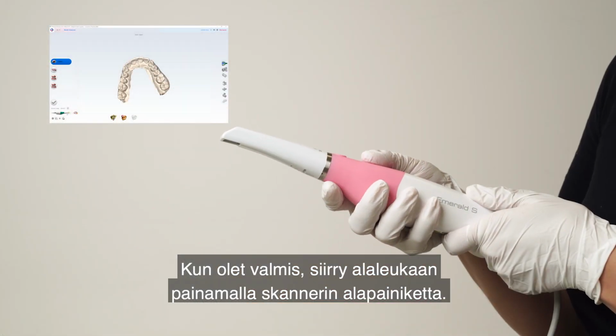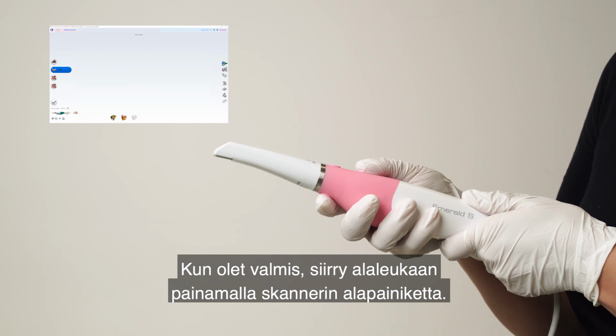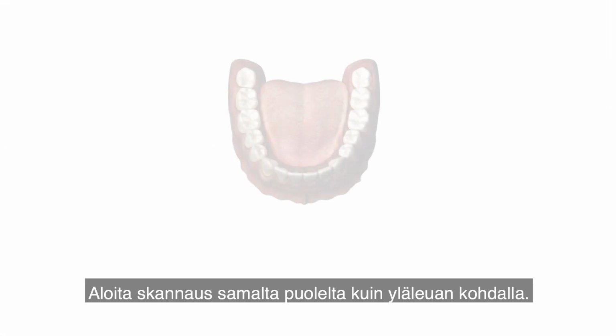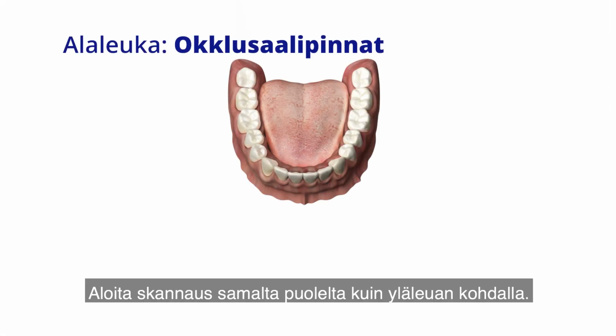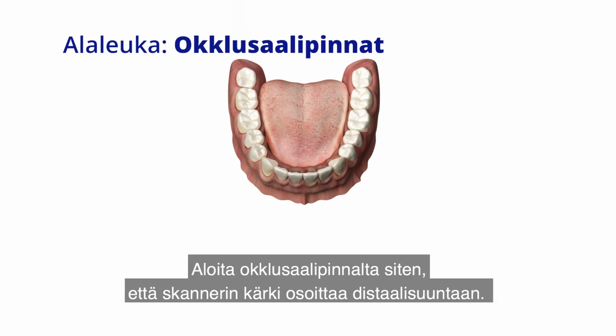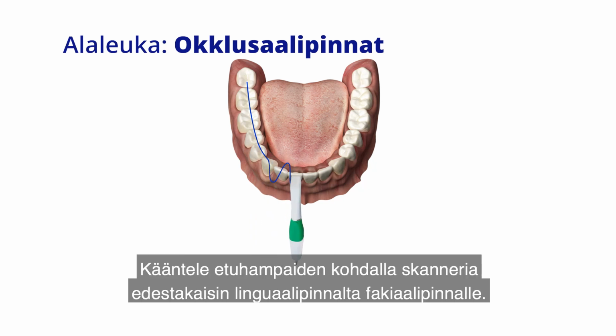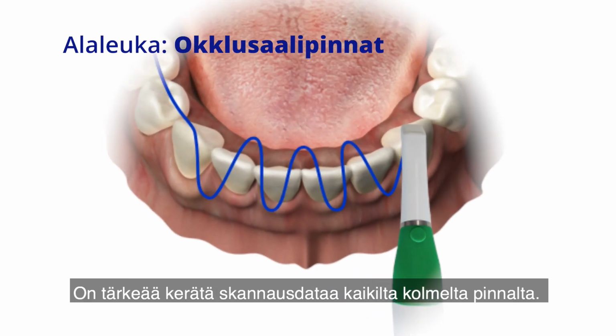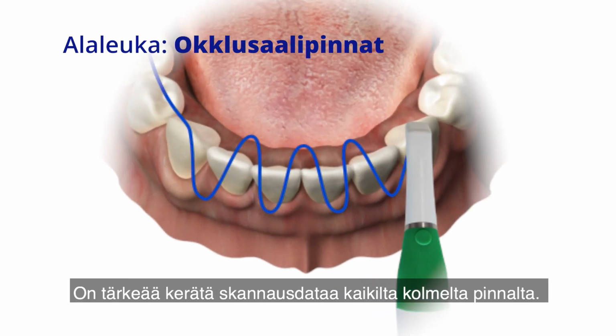Once you're ready, move on to the lower arch by pressing the lower button on the scanner. Start scanning on the same side as with the upper arch. Start from the occlusal surface with the tip of the scanner pointing towards the distal. On the interiors, rotate back and forth from the lingual to the facial. It is important to capture data on all three surfaces.